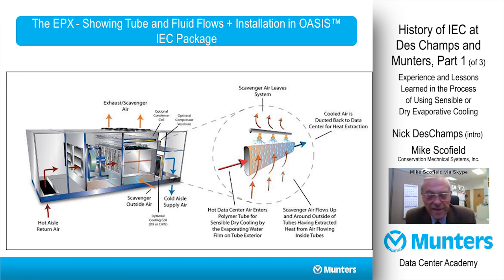One of the reasons that the horizontal arrangement of these tubes was selected is that we increased the wetted surface of the heat exchanger, and the airfoil shape on the wet side reduced the parasitic loss. Since many of these heat exchangers, like data centers, will use a constant flow, by reducing the wet side static pressure penalty, we reduce the parasitic losses attributed to the cooling system.